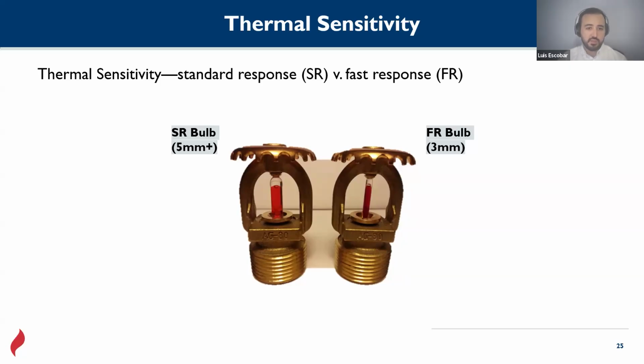Standard response versus fast response. What can you see here between these two sprinklers? The diameter of the bulb is thicker here and thinner here. Which one do you think is standard response? Obviously, it's this one, and the fast response is this one, because the heat takes less time to break this glass, or the thermal conductivity heats the fluid that is inside and makes it explode. That's the way we activate these sprinklers. Fast response and standard response.